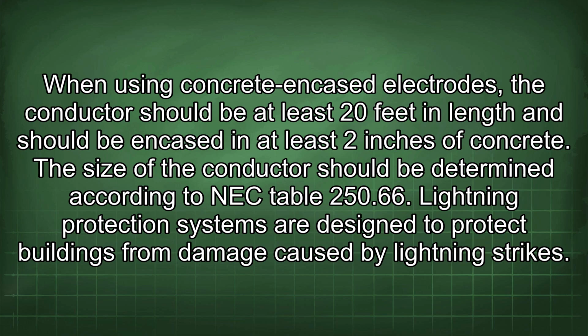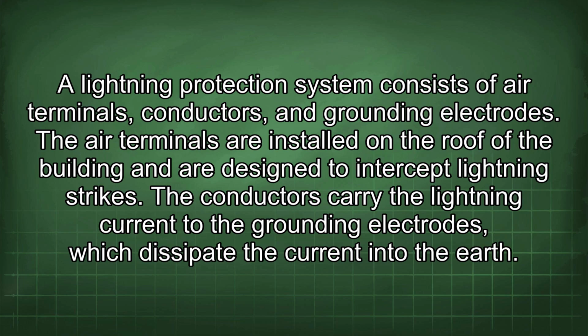Lightning protection systems are designed to protect buildings from damage caused by lightning strikes. A lightning protection system consists of air terminals, conductors, and grounding electrodes. The air terminals are installed on the roof of the building and are designed to intercept lightning strikes. The conductors carry the lightning current to the grounding electrodes, which dissipate the current into the earth.